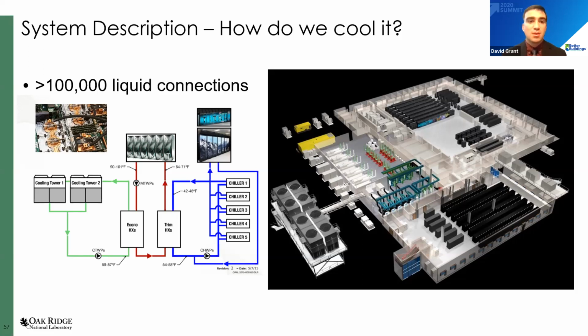Once the water leaves the rack, the water is sent back to our central energy plant, where it comes through the economizing heat exchangers first, which are connected to cooling towers. And on nice, cool, dry days, we're able to cool 100% of the load within the data center with those economizing cooling towers. We are in Oak Ridge, Tennessee, which is hot and humid during the summer, and so we aren't able to do that year round. So we installed trim heat exchangers, which are then connected to our chilled water systems to take the cooling temperature down to that 70 degrees if the cooling towers were not able to do that. Next slide, please.